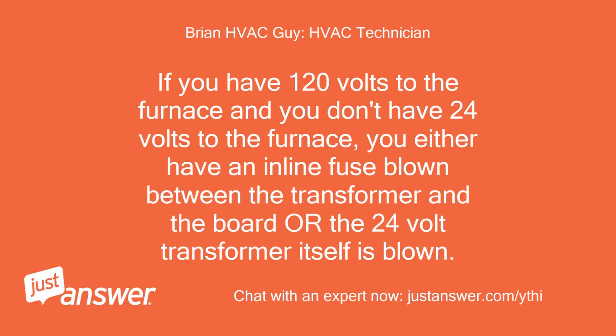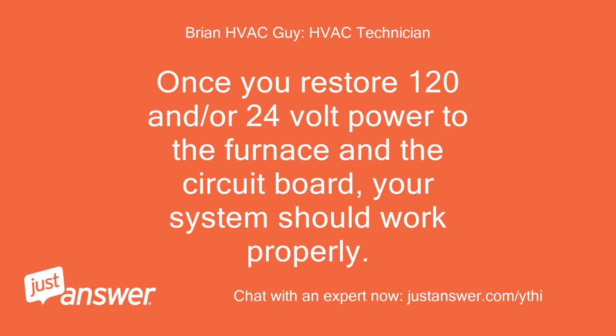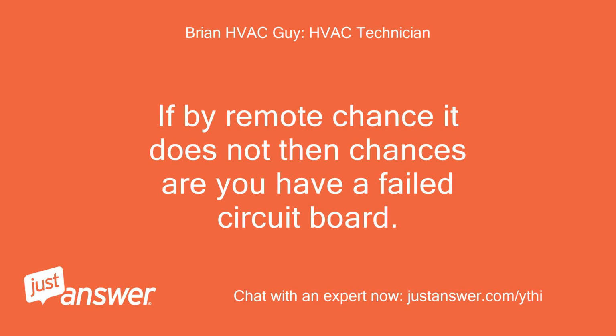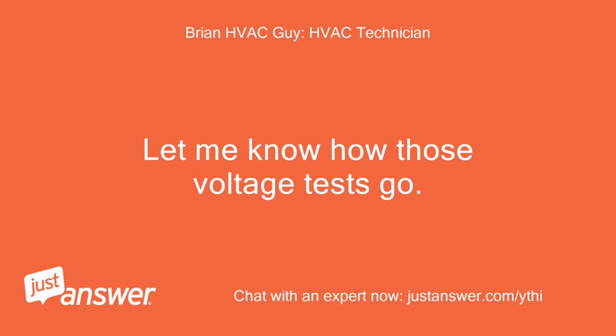If you have 120 volts to the furnace and you don't have 24 volts to the furnace, you either have an inline fuse blown between the transformer and the board or the 24 volt transformer itself is blown. Once you restore 120 or 24 volt power to the furnace and the circuit board, your system should work properly. If by remote chance it does not, then chances are you have a failed circuit board. Let me know how those voltage tests go.